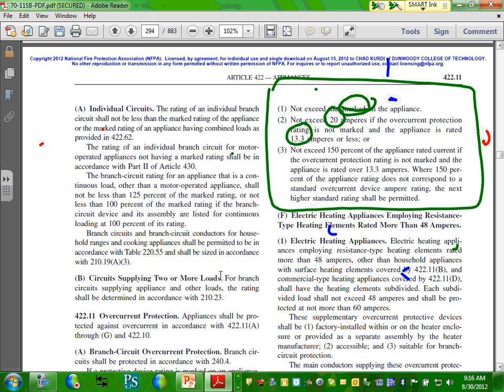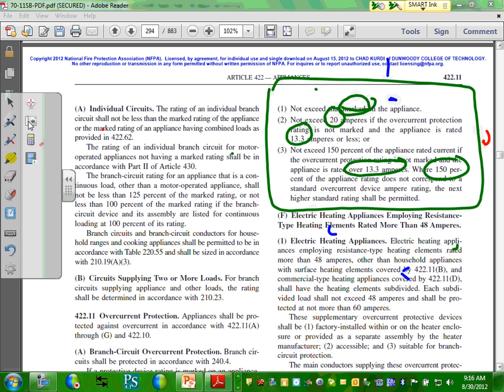Now, if it's more than 13, then they allow you to use this multiplier, 150%. If the full load amp is more than 13, 150%. Thumbs up. So does this apply to us? More than 13 amps? So that's where we're going to get the more than 13. So let's go take a snapshot of that.